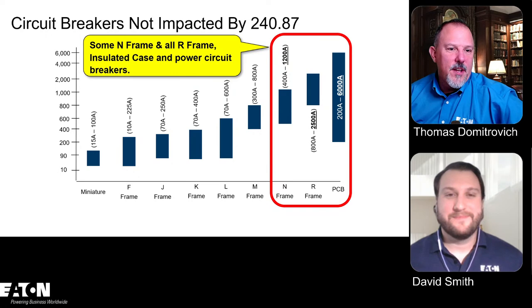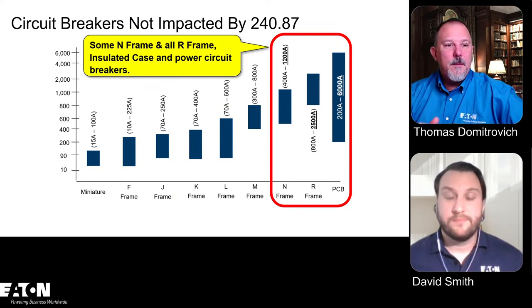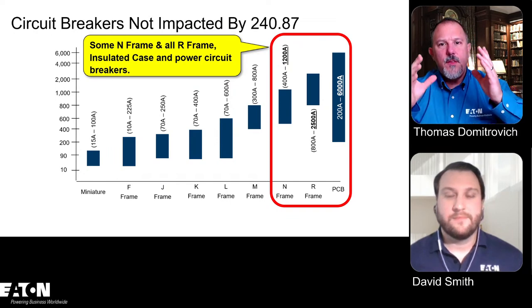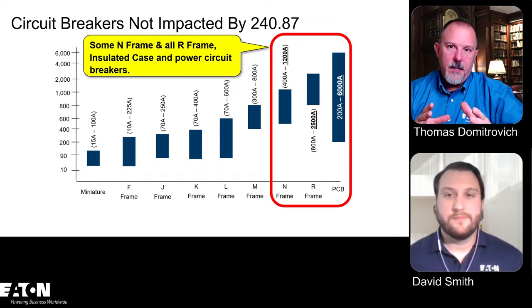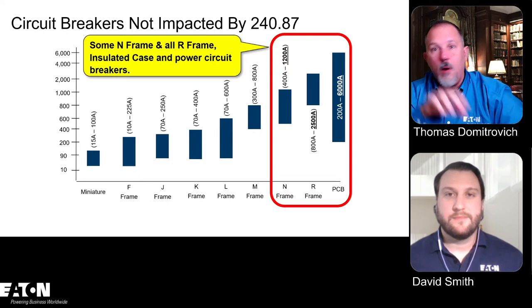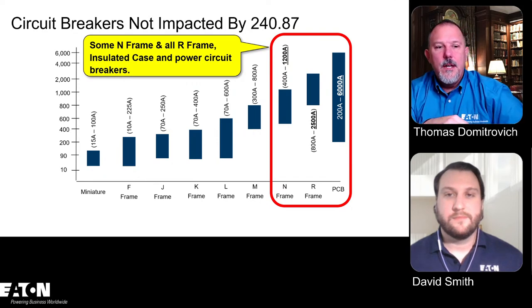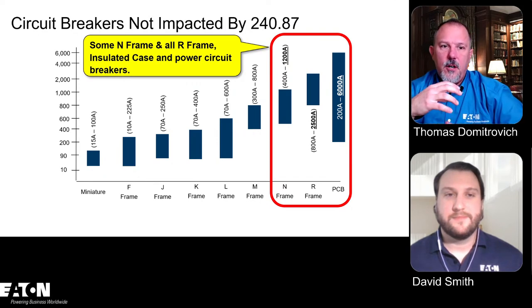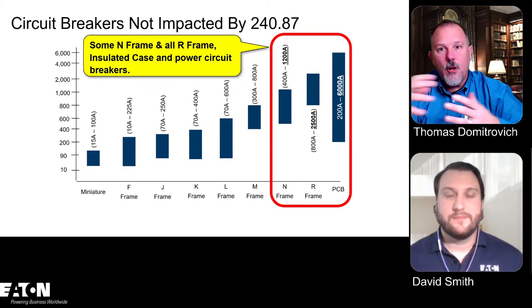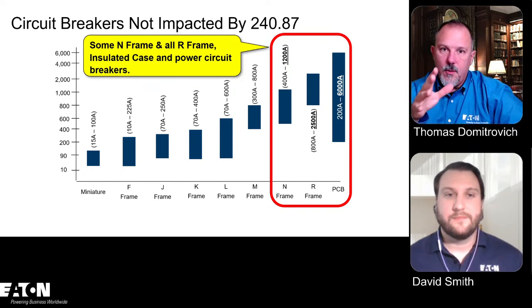He says, actual in front of overcurrent is confusing. If the circuit breaker is only used for short circuit and ground fault, like a motor, this section is not applicable. Or is it related to relay protection, like a genset with internal relay protection? So, Al, a circuit breaker has a trip unit in it. And some of those circuit breakers might have what we call plugs. And every manufacturer is a little different. So it's the overcurrent protection. Can it be adjusted to 1,000 or 1,200 amps?